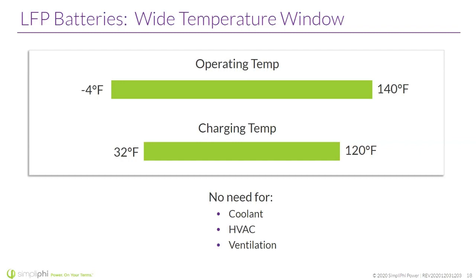Charging for lithium batteries, and this is true for all battery chemistries, not just LFP, has to be slowed down. This gives a charging range that prevents charging from happening below 32 degrees, but you can charge at a very reduced rate. If you have an advanced battery management system, such as the Amplify battery or the SimpliPhi battery, you can actually charge these batteries at slow rates at low temperatures. So our batteries with the advanced battery management system do allow charging, it's just drastically slowed down.